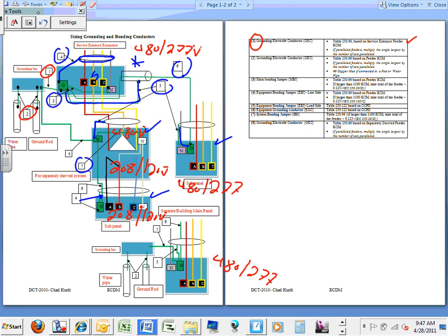Where's number 8? Let me see the sheet. Number 8, yeah, grounding electrode conductor right here. Number 8, grounding electrode conductor for the separately derived system. That's for the separately derived system. Any question, guys, about this? And the same numbers are identical. If you look at wherever you see a 6, you size it basically the same. Wherever you see a 1, you size it the same way. So if you look, guys, I have a 6 here and a 6 here. It's the same equipment grounding conductor for different panels.